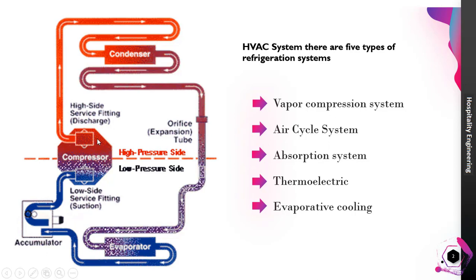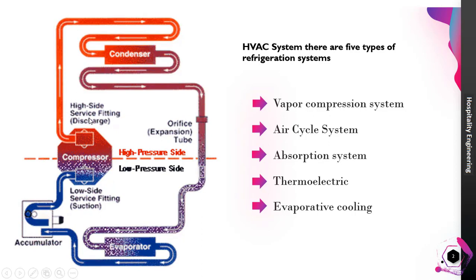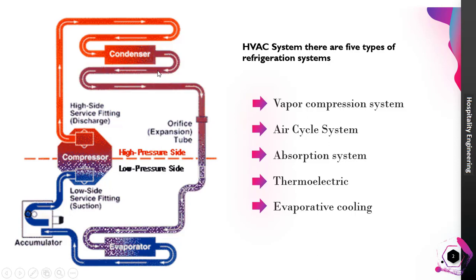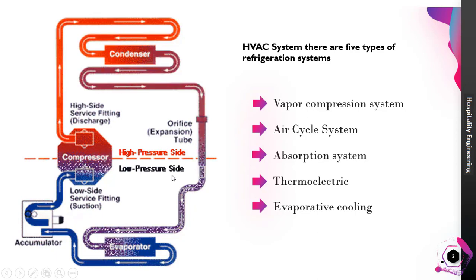The main component of the Vapor Compression System is the compressor. The compressor is the heart of the system. It receives the low-temperature, low-pressure refrigerant and compresses it to high-pressure, high-temperature refrigerant, which goes to the condenser. In the condenser, condensing is happening — a high-pressure, high-temperature gas condenses into a high-pressure, high-temperature liquid. The liquid then moves to the expansion tube or expansion valve, where the pressure is reduced.